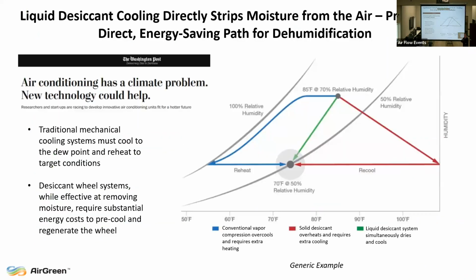On the regen side, you're heating up in order to remove the moisture from the desiccant, evaporate it essentially. How is it discharged? It's going into the discharge air most of the time. If we have a 100% outdoor air system, we usually tie it in with an air-to-air heat exchanger, and all the exhaust air out of the building, that moisture will go into that exhaust air. For a growing facility, that's usually completely separate and it's all outside to begin with.